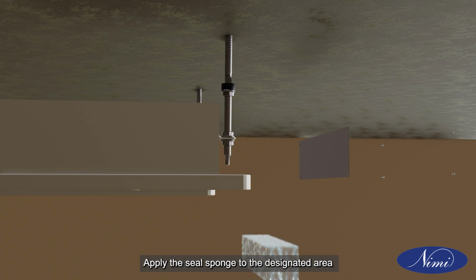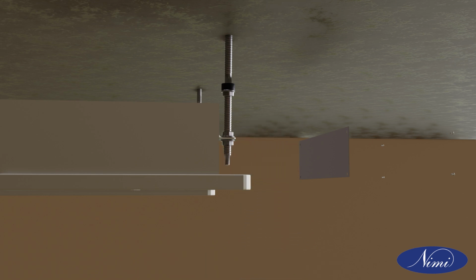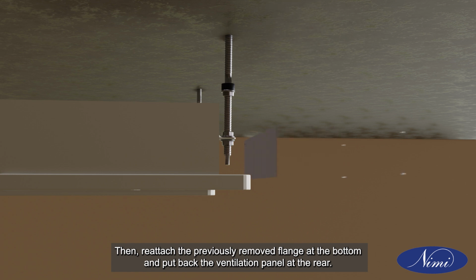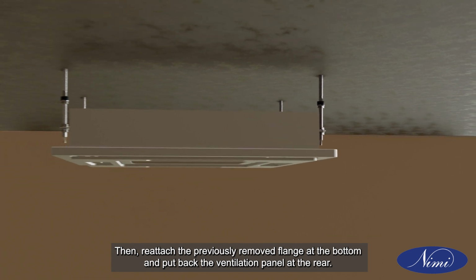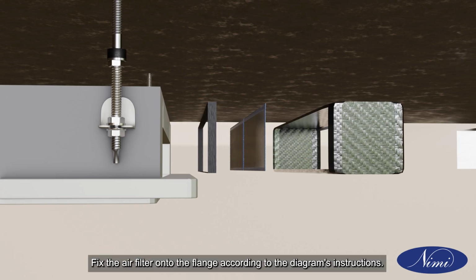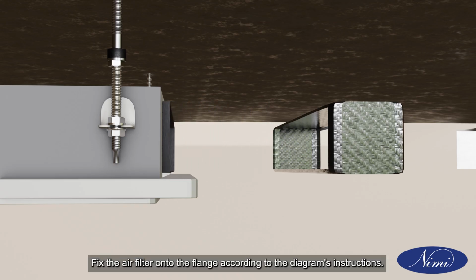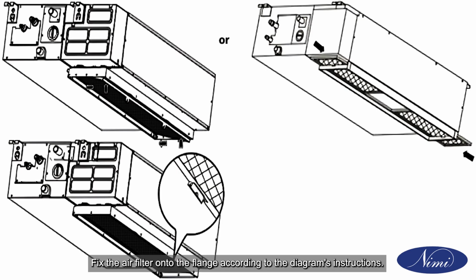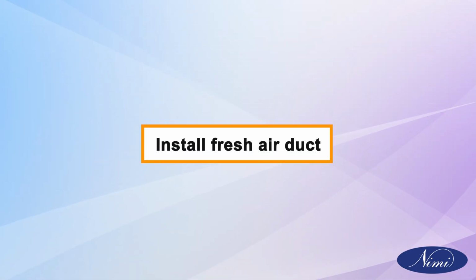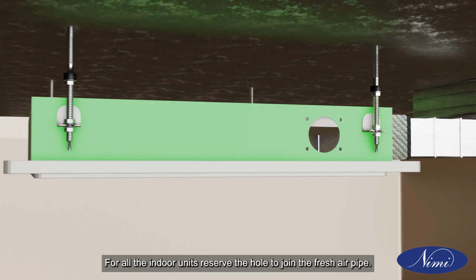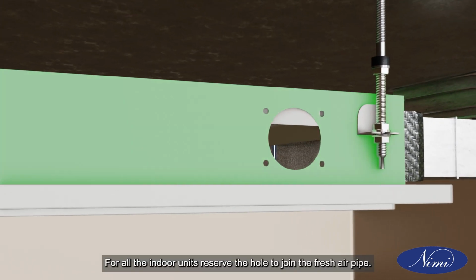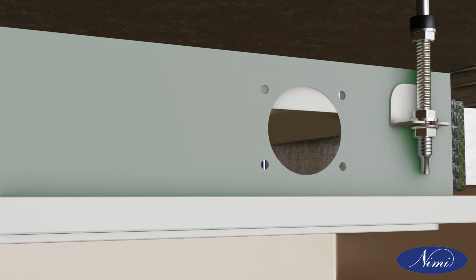Apply the seal sponge to the designated area. Then, reattach the previously removed flange at the bottom and put back the ventilation panel at the rear. Fix the air filter onto the flange according to the diagram's instructions. Install fresh air duct. For all the indoor units, reserve the hole to join the fresh air pipe. The hole sizes are as follows.